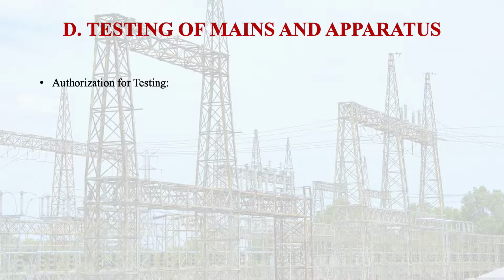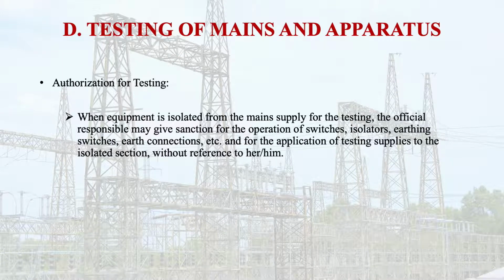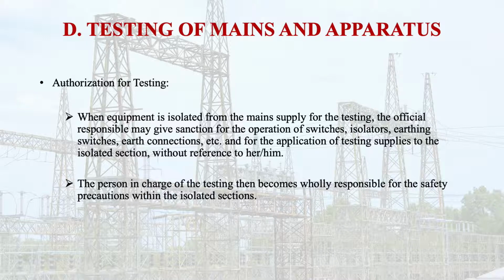Then, authorization for testing. When the equipment is isolated from the main supply for testing, the official responsible may give sanction for the operation of switches, isolators, earthing switches, earth connections, etc., and for the application of the testing supplies to the isolated section without reference to him or her. The person in charge of the testing then becomes wholly responsible for the safety precautions within the isolated section, but no switch or isolator connecting any isolated section to the main supply system should be operated without direct sanction of the responsible official, except for the purpose of obtaining testing supplies.